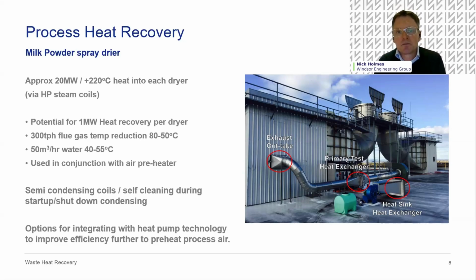We pulled out a small component of the exhaust gas, put it through a small coil that you can see in the middle there. It's actually 2 coils to allow as much heat as possible to be recovered. We were condensing the moisture in the air there. One of the biggest risks that the end user saw was the fouling contamination of that coil with the small amount of particles that come through from the spray dryer. But this proved that wasn't the case. It was actually sort of self-cleaning. The semi-condensing nature of it meant that it was washing away any of the powder that collected. So it ran for a full season, proved its purpose.